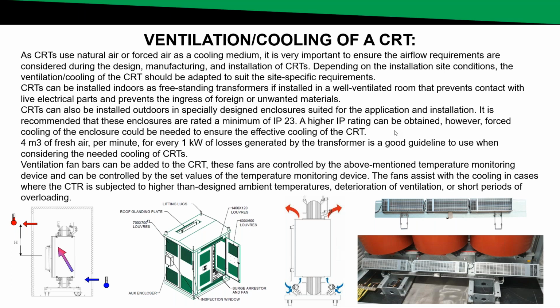Ventilation bars are also available that can be fitted at the bottom of the cast resin transformer. These ventilation bars are controlled by the previously mentioned temperature monitoring device. These fans only assist with the cooling in cases where the cast resin transformer is subjected to higher than designed ambient temperatures and/or the deterioration of ventilation or even short periods of overloading.